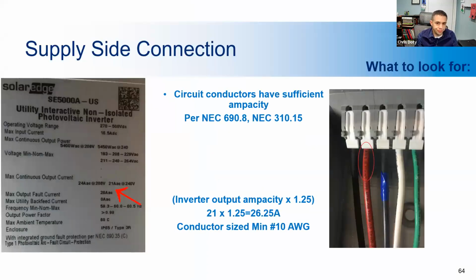So keep moving through. With the supply side connection, you also have to ensure that the conductors are sized appropriately, as you do throughout the whole system. You verify this by looking at the inverter nameplate for the max continuous inverter current output. Just like with the load side connection, you multiply that by 125%, and verify that the conductor size stamped on the wire can accommodate that. And as I said, there are tables you can look up to verify that the wire can handle that amperage.